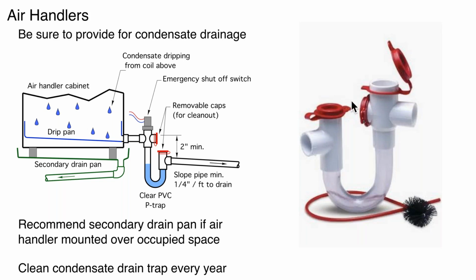Again, just a close-up of the trap. Here's the brush that comes with it. Here are the clean out caps. Sometimes there are 2 of them. I do recommend that you order them with that emergency switch so that you can prevent that air handler from operating if you get a blockage in that drainage system.